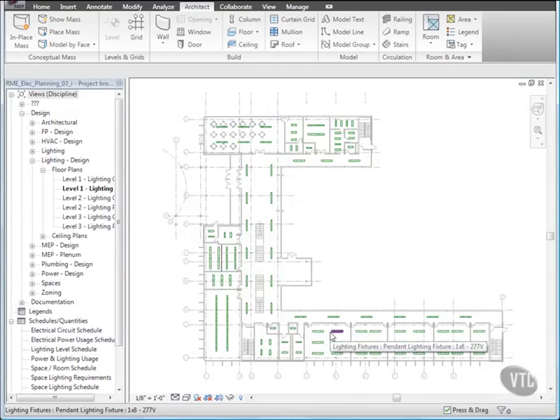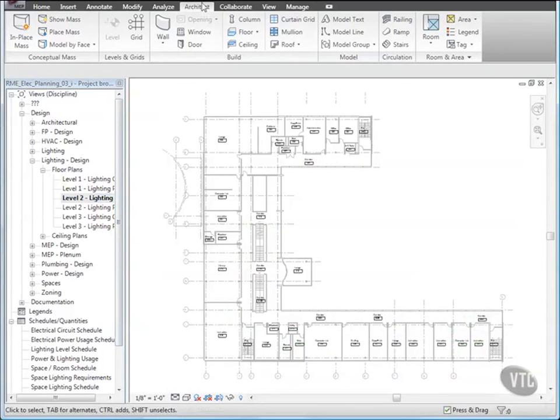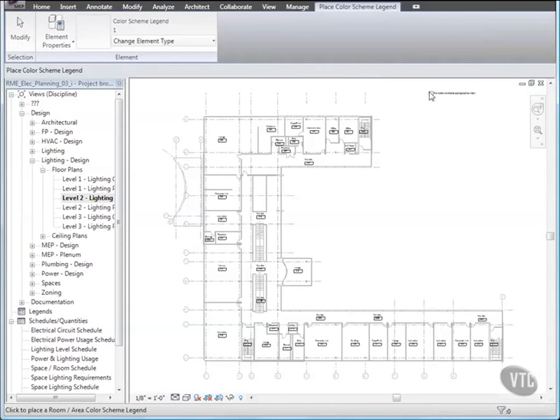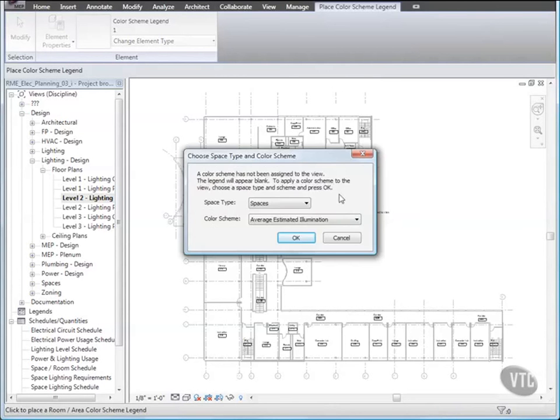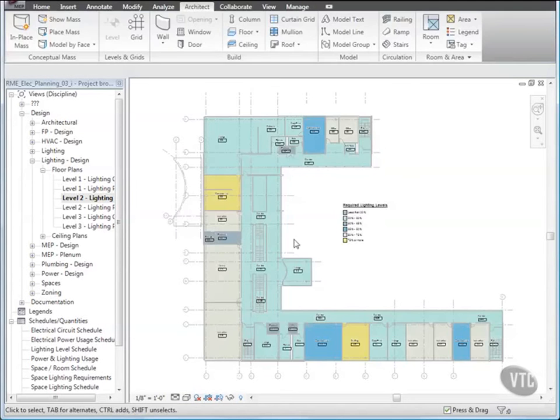And next, we'll add a Legend and apply the Color Scheme. In the Project Browser, under Lighting Design Floor Plans, open the View Level 2 Lighting CF. Then, click the Architect tab, and from the Room and Area panel, click Legend. Then, click to the right of the drawing as shown. And in the Choose Space Type and Color Scheme dialog, for Space Type, select Spaces, and for Color Scheme, select Required Lighting, and click OK. When you do, the Color Fill Plan displays the required Illuminance Levels based on the key values previously created.